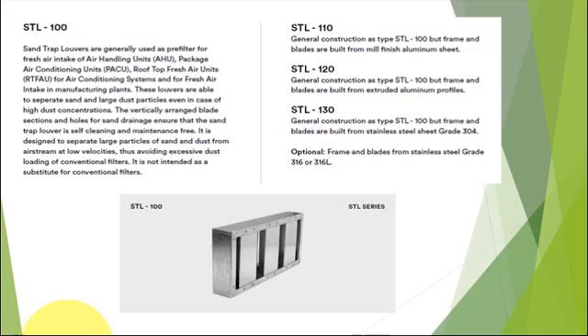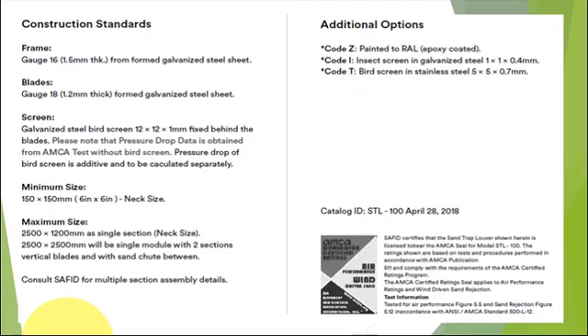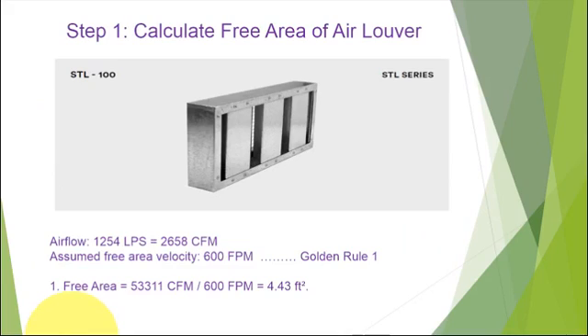Let's go through the procedures to size the proper sand trap louvers. For normal operating conditions, sand trap louvers should be selected for a maximum free area velocity of 600 feet per minute — this is the golden rule for sizing any sand trap louver. The first step is to calculate the required free area, which is the required airflow through the sand trap louver divided by 600 feet per minute. This gives you 4.43 square feet.